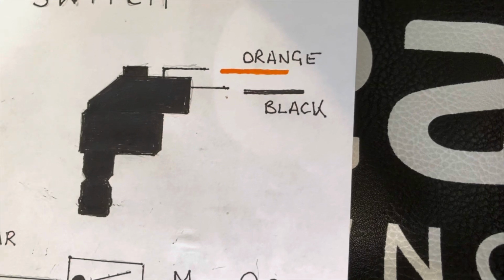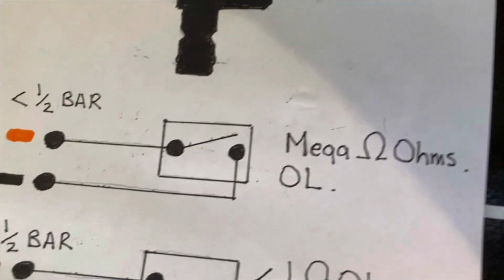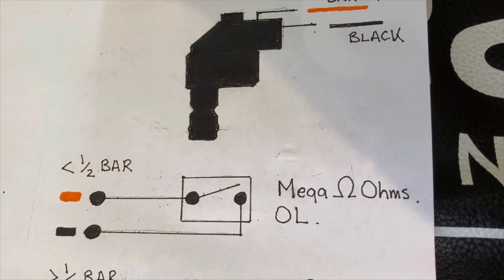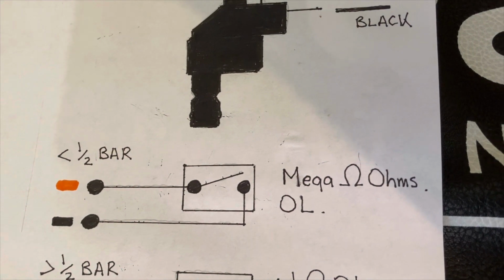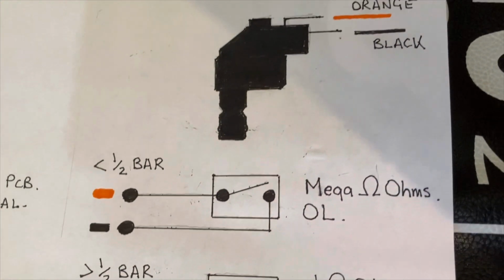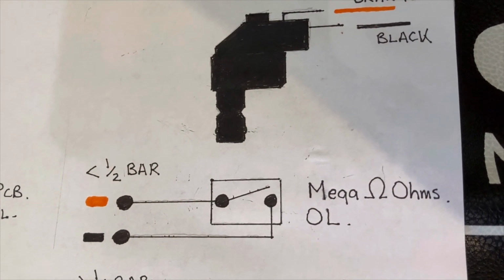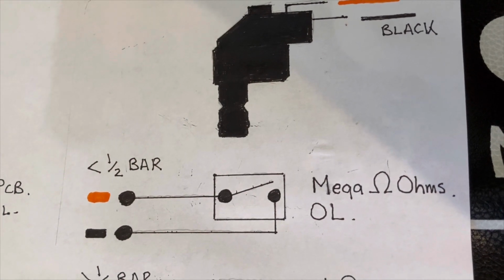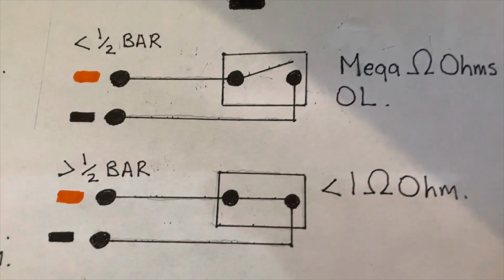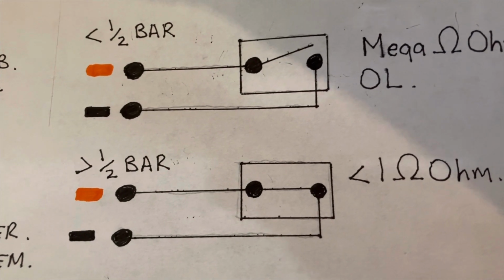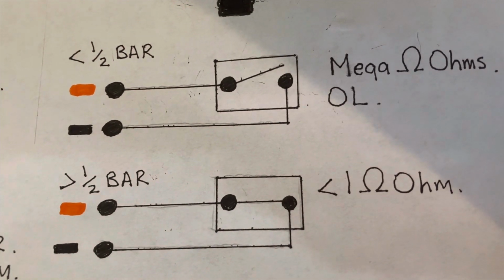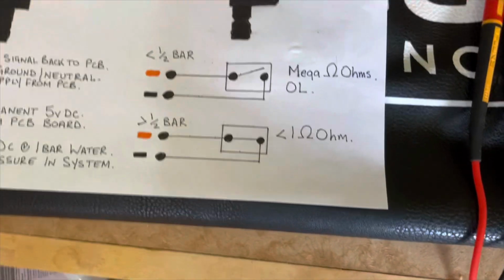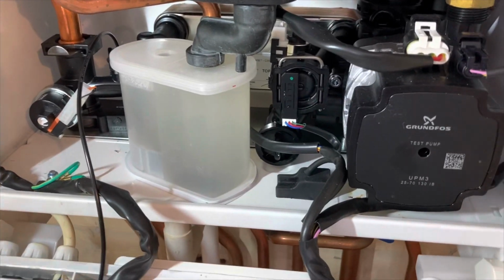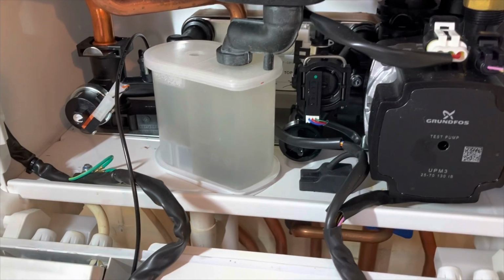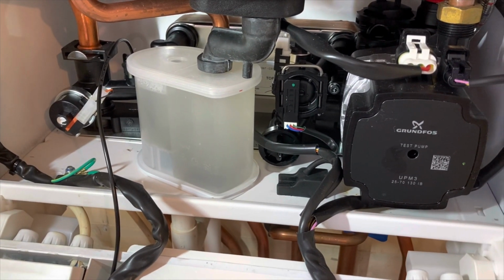It's quite straightforward. I've put orange and black on here, but it's got 2 wires, quite straightforward. As you can see, below half a bar, the circuit opens. So if you've got less than half a bar in the system, between orange and black, you'll probably read mega ohms, or open line, open loop, some people call it. If you've got greater than half a bar in the system, the circuit will close, creating the circuit, and you'll get a reading of less than 1 ohm. That's how we measure it. What I'll do, I'll set up my multimeter and we'll do some actual measurements to show you how it exactly works.